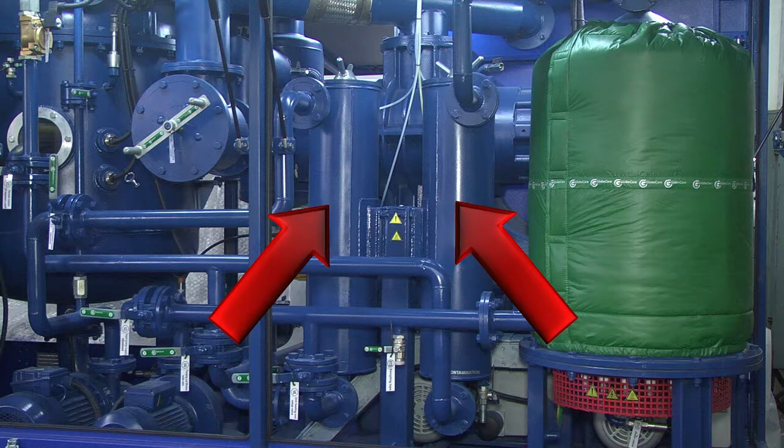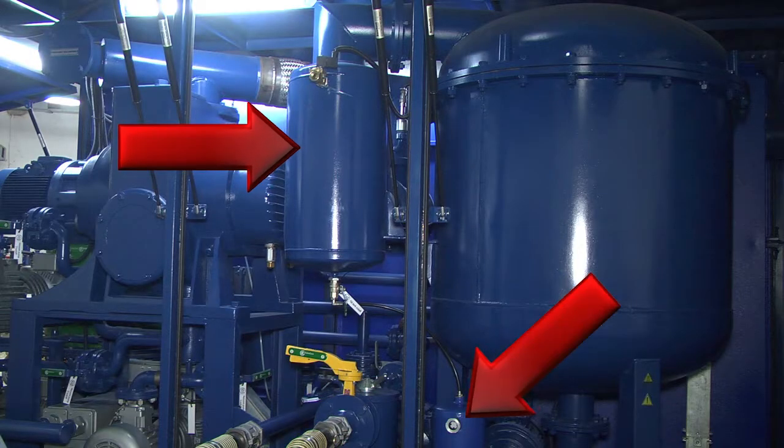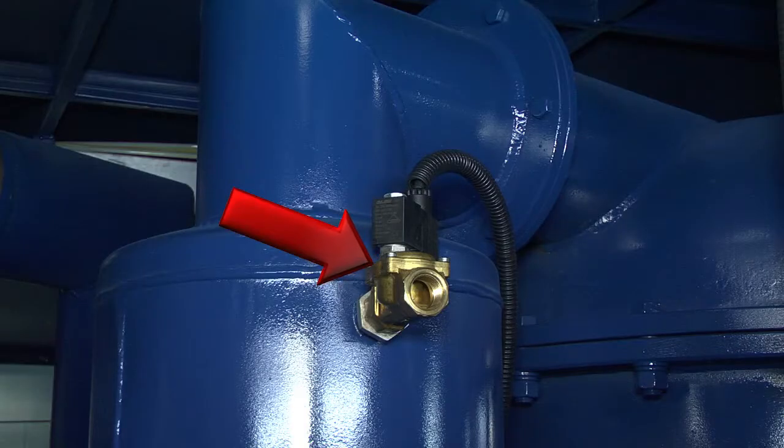It is easy to maintain, has large oil treatment area, stable oil treatment parameters, allows for visual monitoring of filter contamination. Oil trap with reservoir, which features protection of vacuum system from oil, protection of vacuum column from foaming, provision for entry of air during transformer oil treatment, possibility to drain oil from the receiver without stopping the treatment process. The oil trap features a solenoid valve to allow entry of air during an automatic mode of operation.